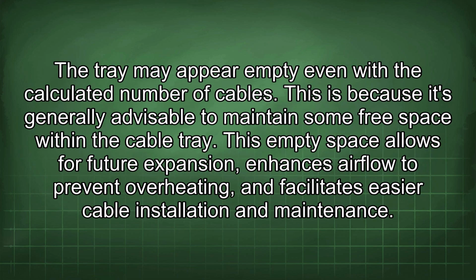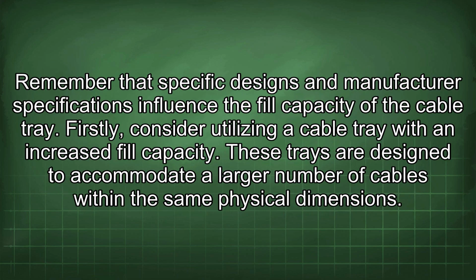The tray may appear empty even with the calculated number of cables. This is because it's generally advisable to maintain some free space within the cable tray. This empty space allows for future expansion, enhances airflow to prevent overheating, and facilitates easier cable installation and maintenance. Remember that specific designs and manufacturer specifications influence the fill capacity of the cable tray.